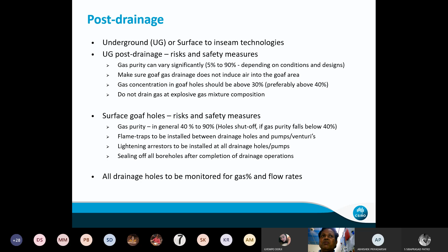Flame traps are to be installed between drainage holes and pumps and venturis. Lightning arresters should also be installed at all drainage holes. Sealing of all boreholes after completion of drainage operation: after draining out the methane gas, the boreholes are to be sealed up so that no gas will come out. All drainage holes are to be monitored for what percentage of gas is there and what the flow rate is. The drainage holes are to be monitored regularly, continuously.